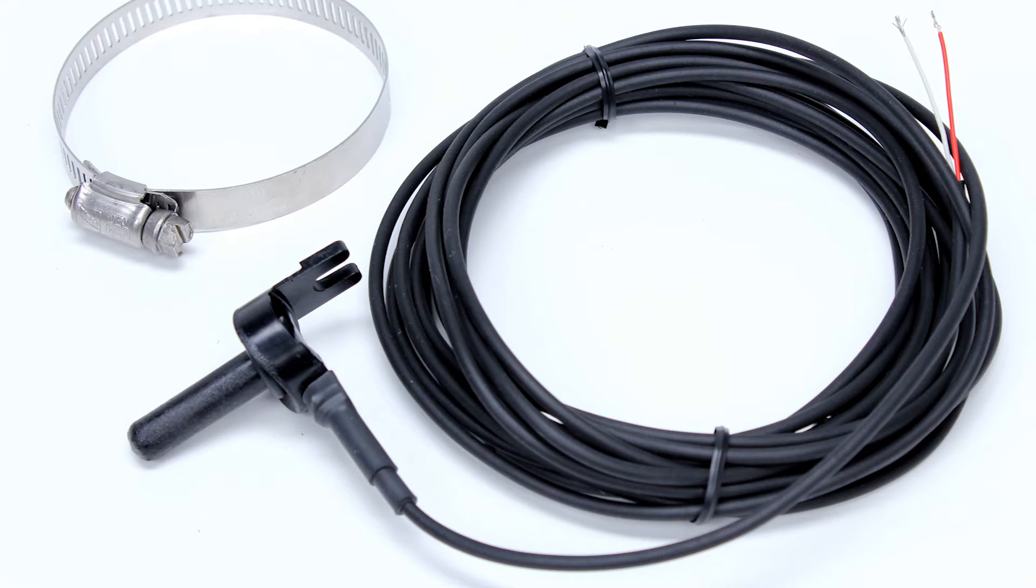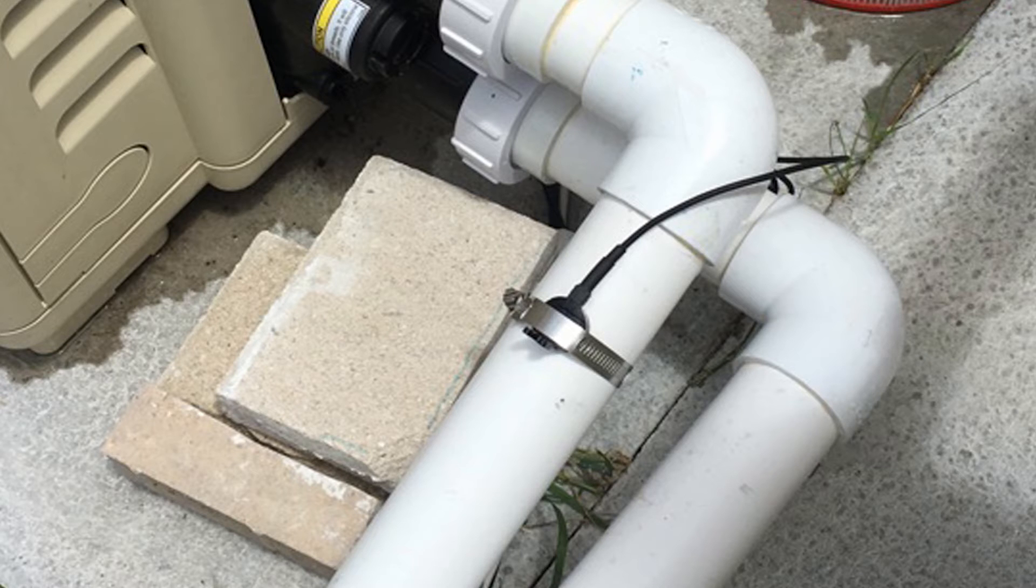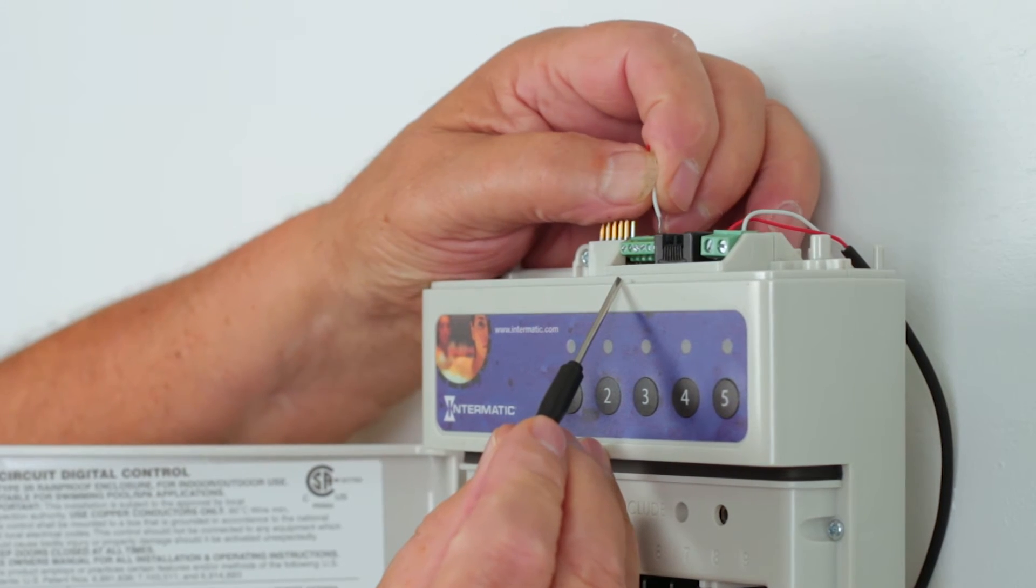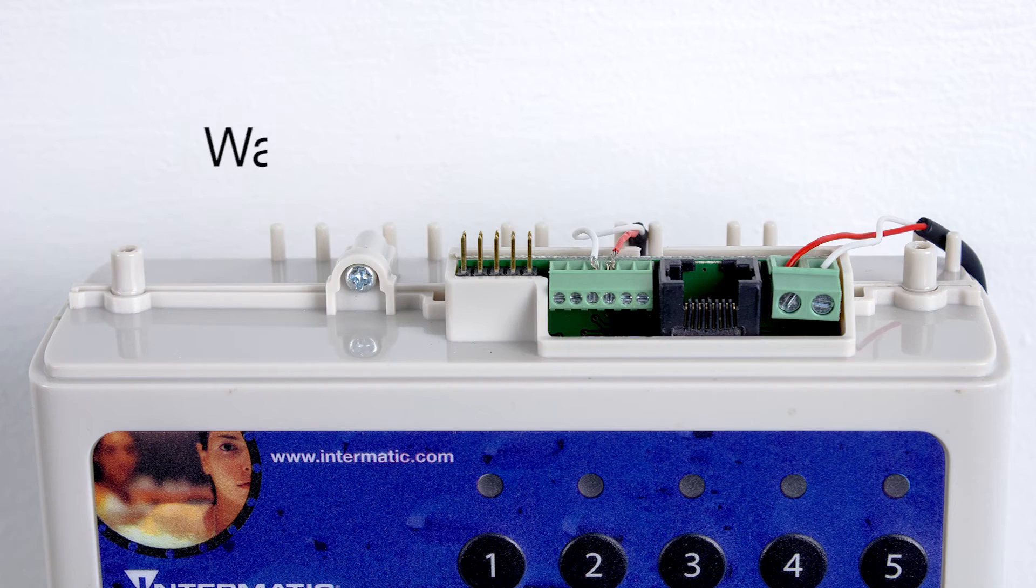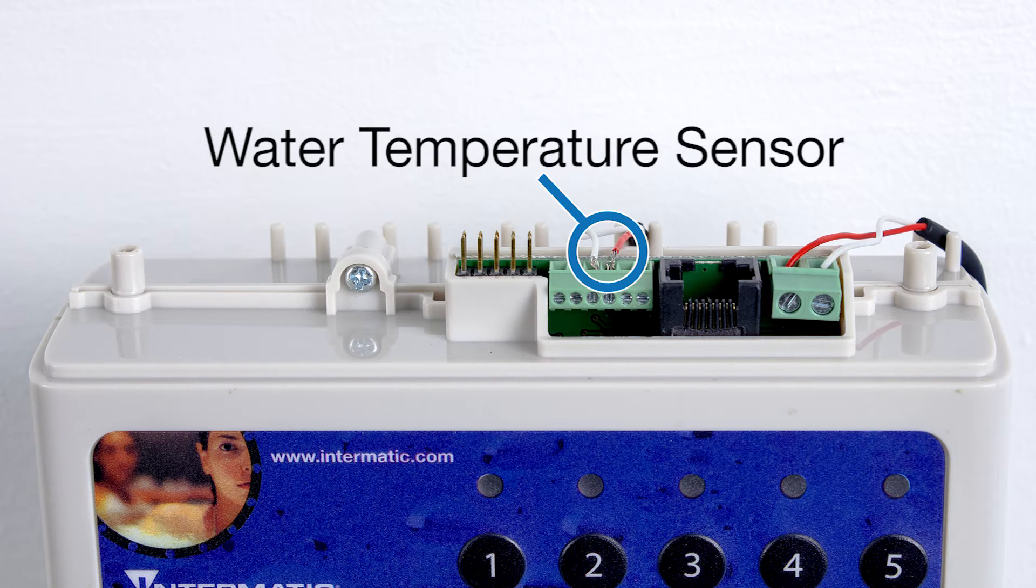Now we can wire the water temperature sensor. Make sure the location for the probe is after the filter, but before the inlet to the heater. Drill a 3/8 inch hole and insert the water sensor probe. Secure it with the provided hose clamp. Make sure the probe's O-ring is in place. Run the sensor wires to the receiver and insert both wires to the middle terminals on the six-pin terminal block. These are not polarity sensitive.